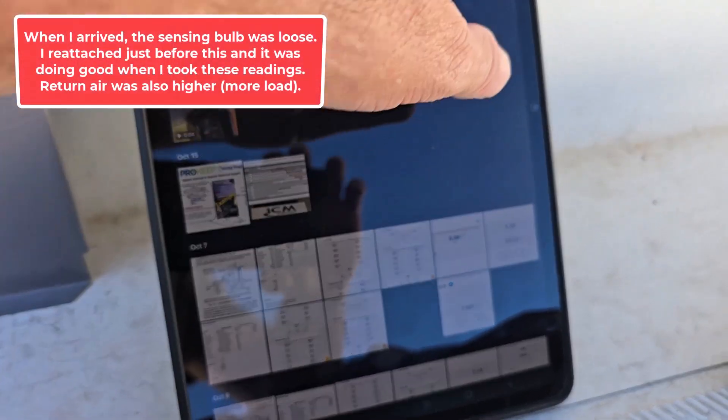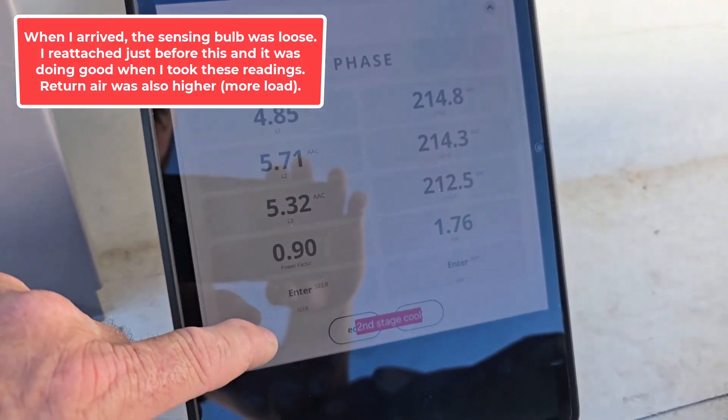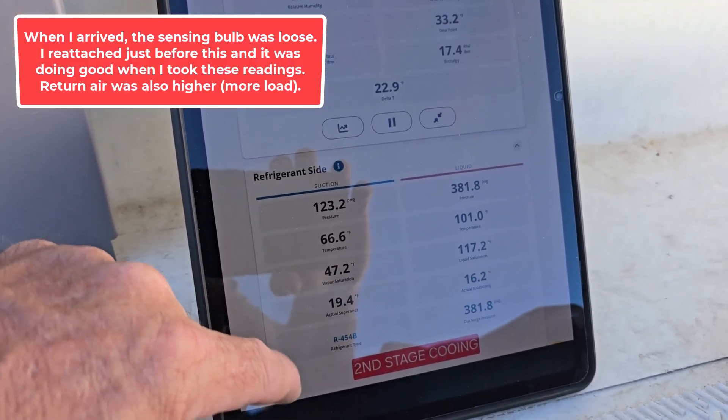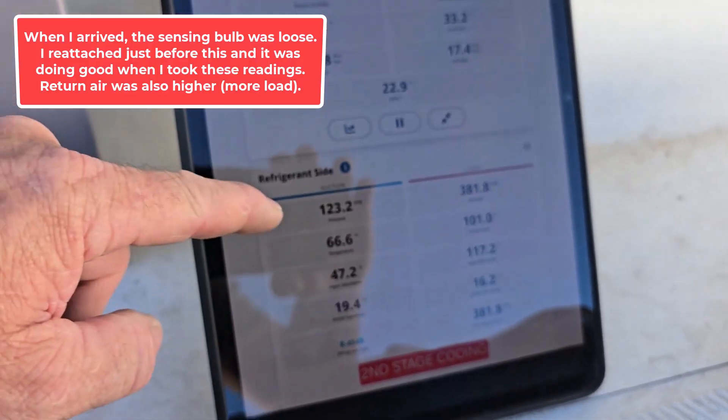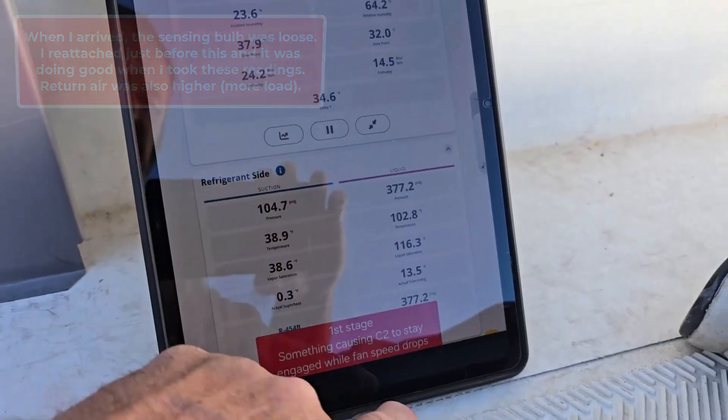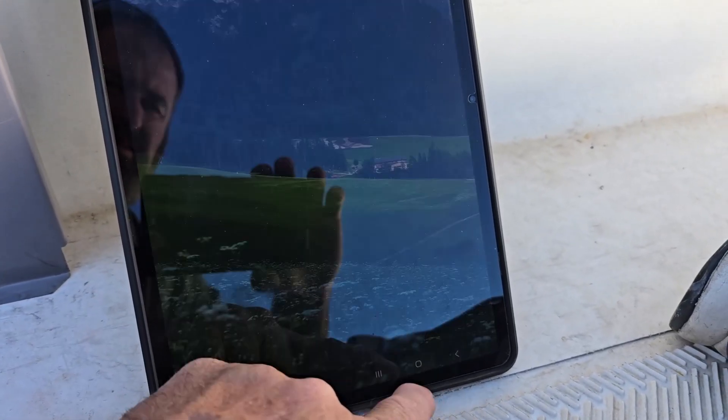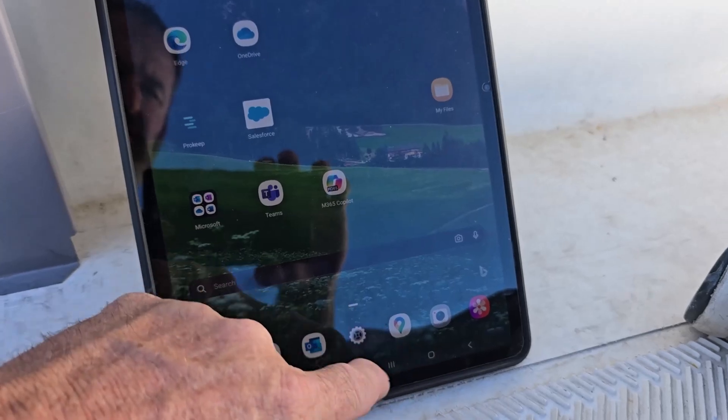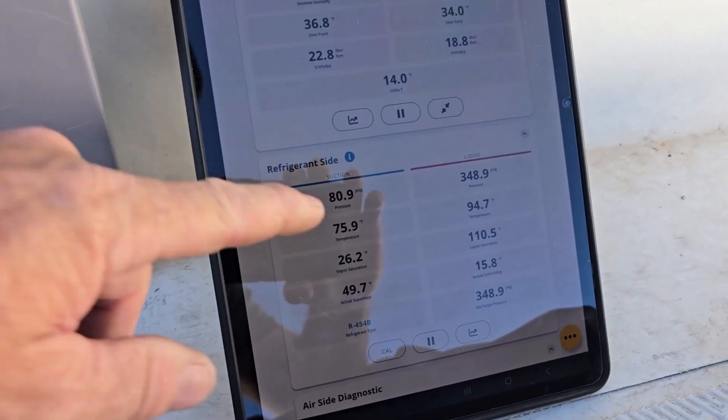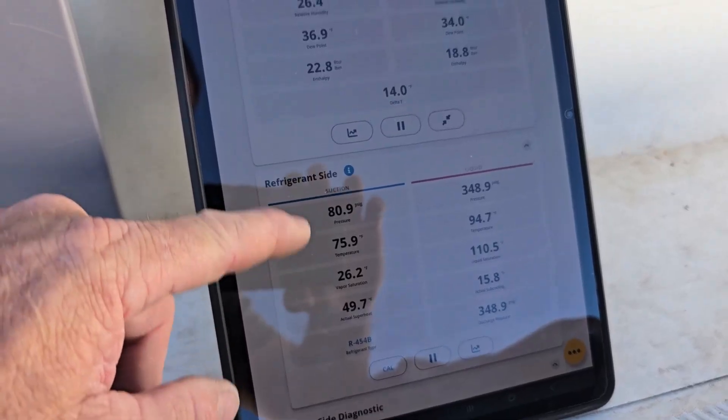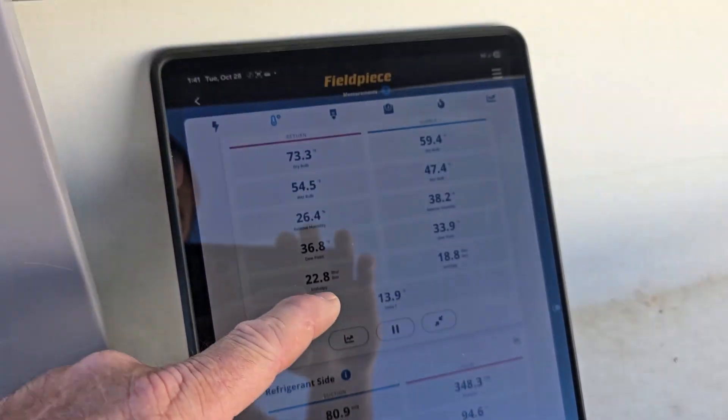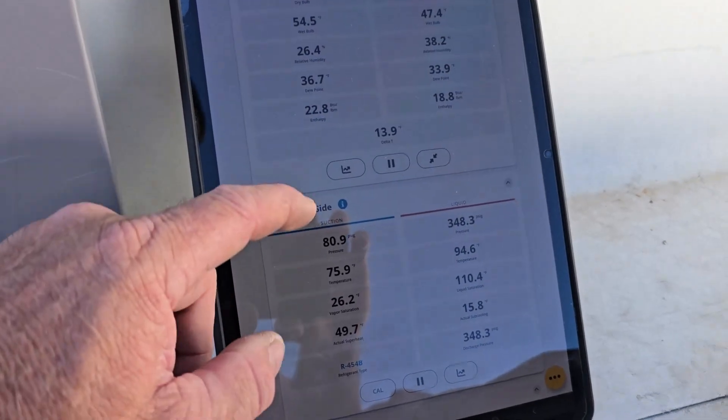And I had, oops, look at my notes. The pressures were great. Funny man. That is strange. 81, 80, 80. That TXV ain't wanting to throttle open. It's stuck about 14 split.